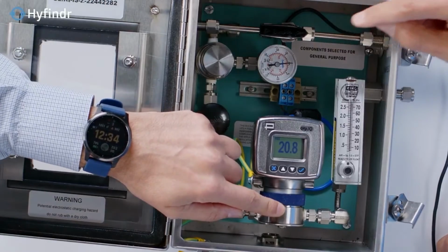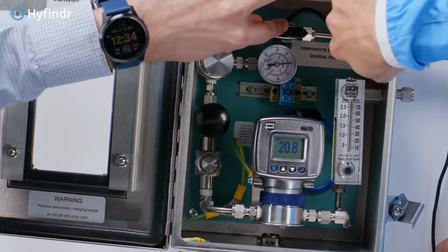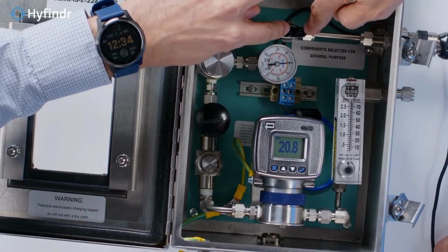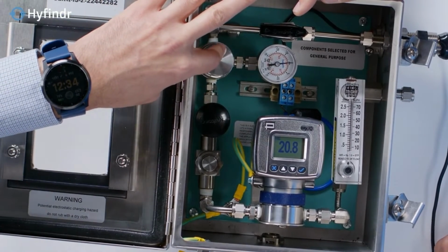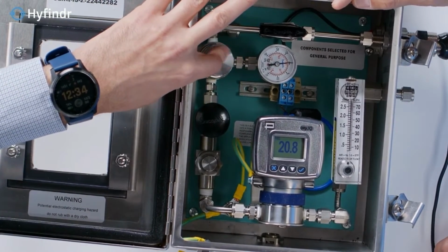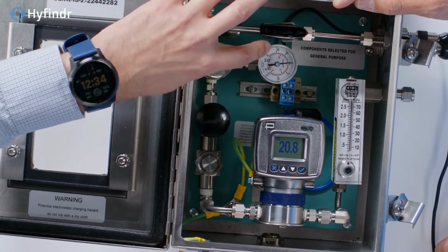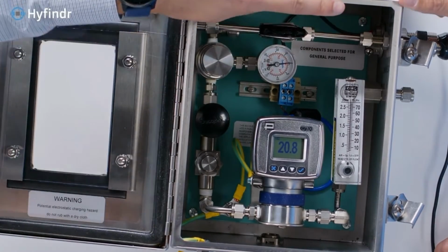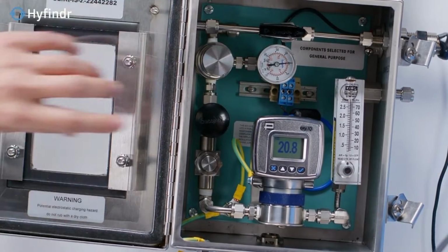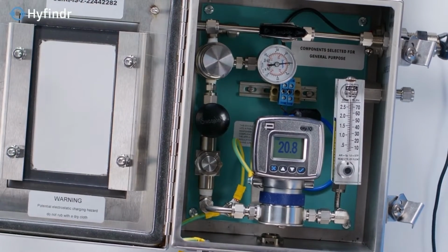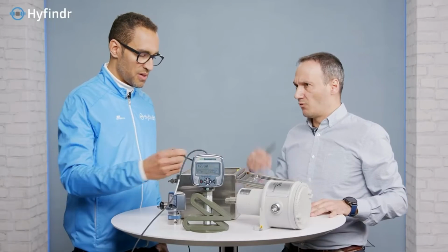Where's the gas coming in then? From this side. That's the sample inlet. And then we have the 3-valve here. That's open. Then we have the pressure regulator. We regulate with that. Before we start, the first thing we close this one. Then we regulate the pressure, look at the pressure gauge, so that the pressure is at the maximum set here. 400 psi-G or 27.5 bar-G. That's like overpressure, I would say.